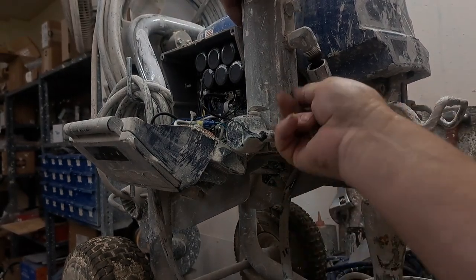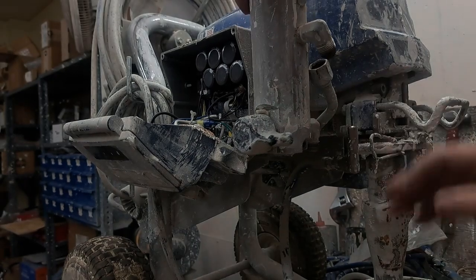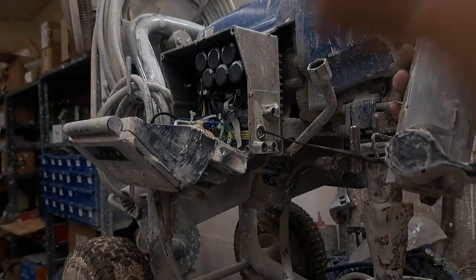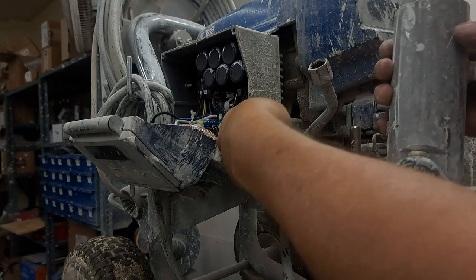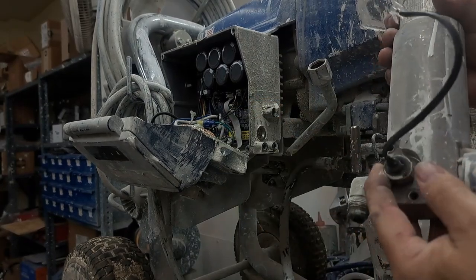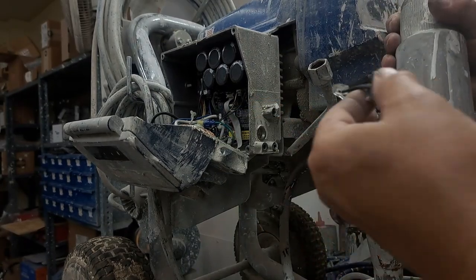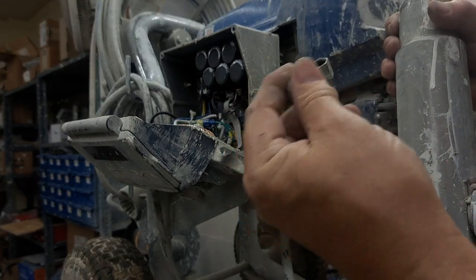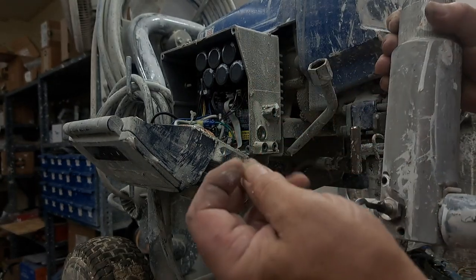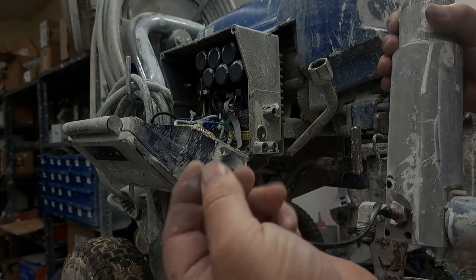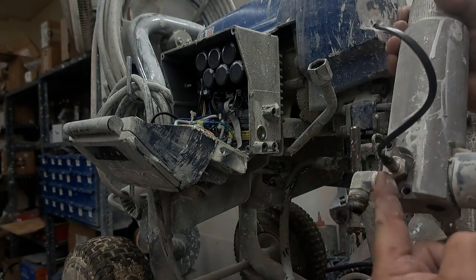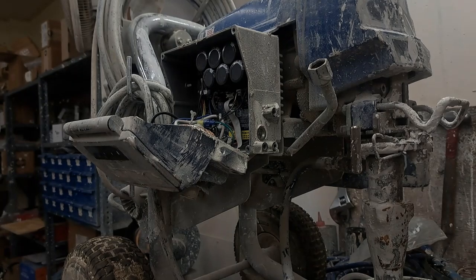Pull them out. Carefully pull this away. Watch the little clip on the inside. Pull it out. There's an O-ring right there. We're going to save that. That's just a buffer against the transducer, back of the transducer in the box. I'm going to save that. 3/4 inch wrench. We'll take this off.